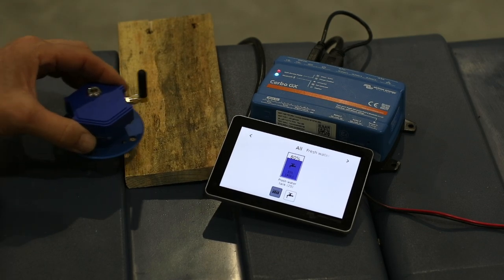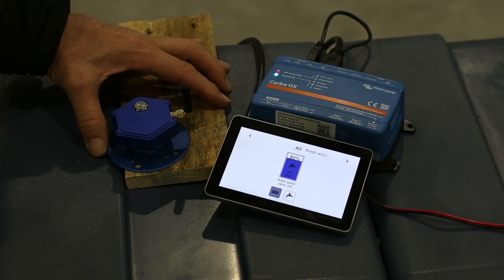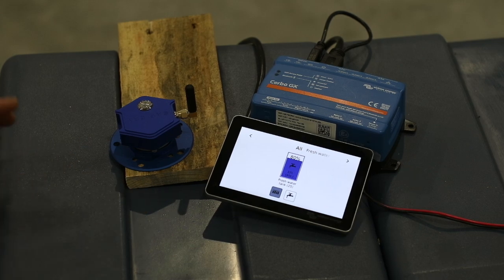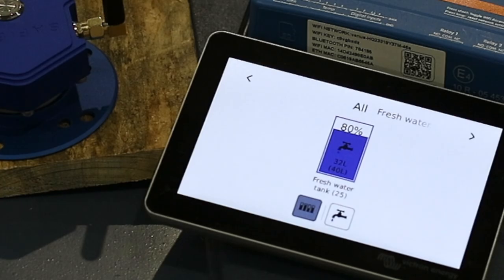To simulate a fiberglass tank, I'm going to put this piece of timber in here and put the sensor on top of the timber. There's a bit of an air gap in there. It's at a slight angle, so this is a worst-case scenario.